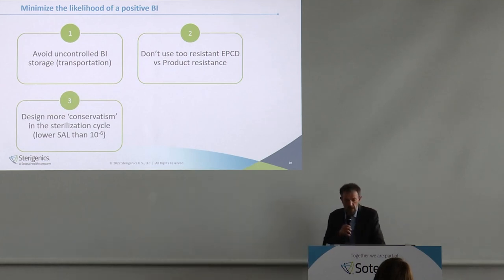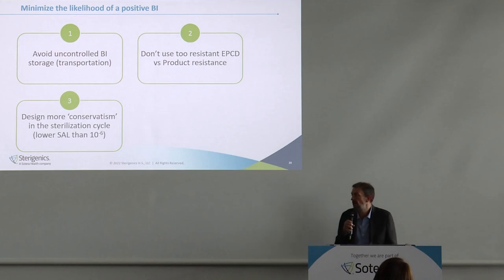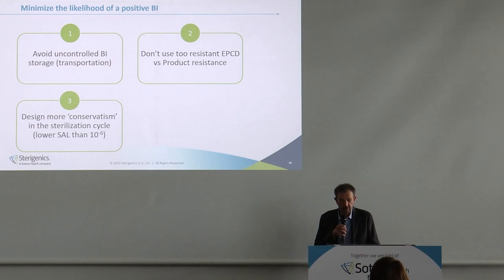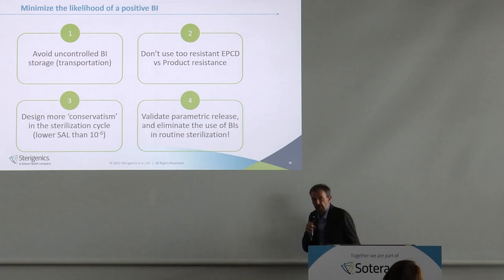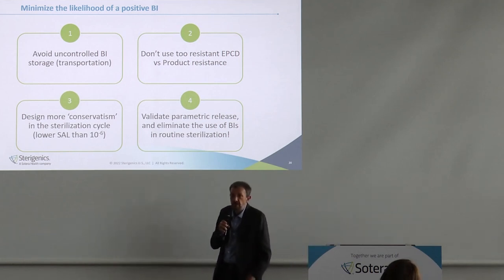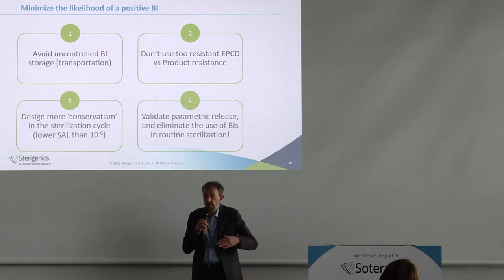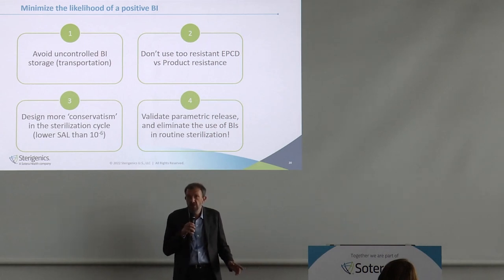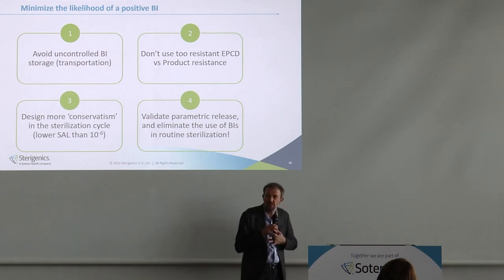If we think about the true bioburden in validation, most of the time we are at 10⁻²⁰ or 10⁻³⁰, which is very conservative. The best approach, in my personal opinion as a non-microbiologist, is to validate parametric release — where we no longer use BIs and instead just check the parameters to release a load. I trust the calibration of a device more than a living microorganism, but I may be wrong — that's my personal opinion.